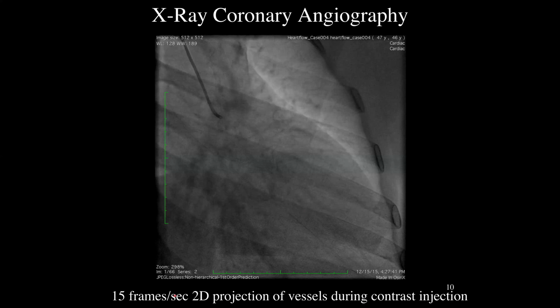Normally, in this case, it's 15 frames a second, and the X-ray pictures are derived from an X-ray flash. You don't keep the X-rays on for that whole 1/15 of a second. You just do a flash and do that 15 times a second. So the flashes are millisecond long, right? So you freeze motion. And here's the ribs background, and then this is the heart.